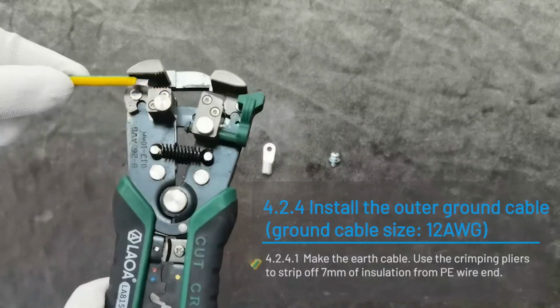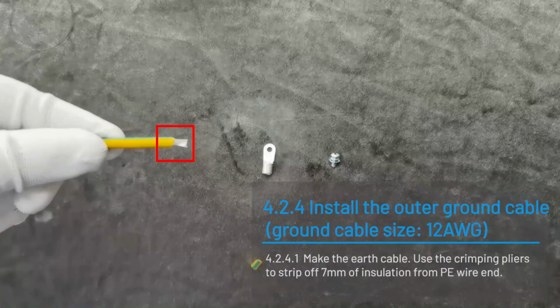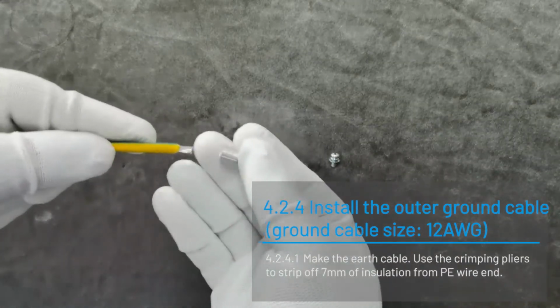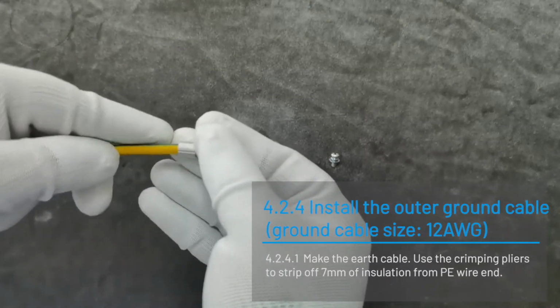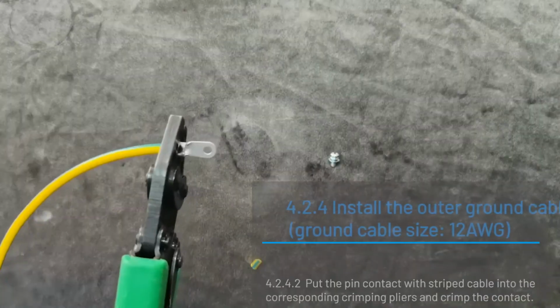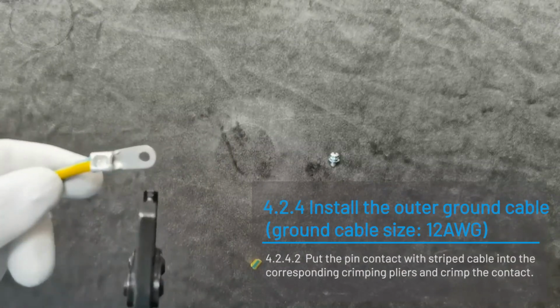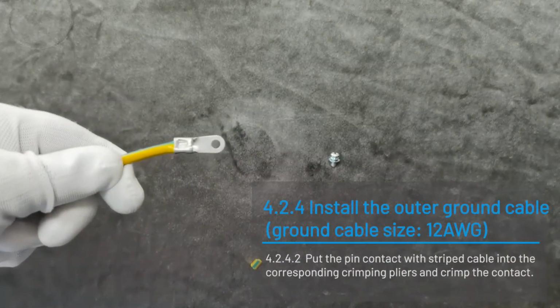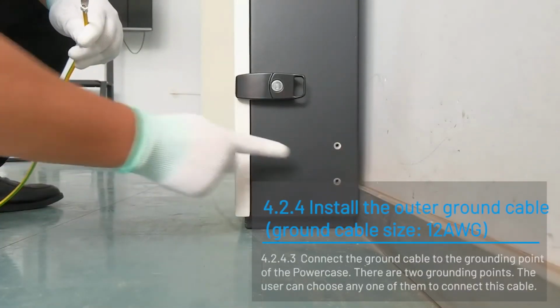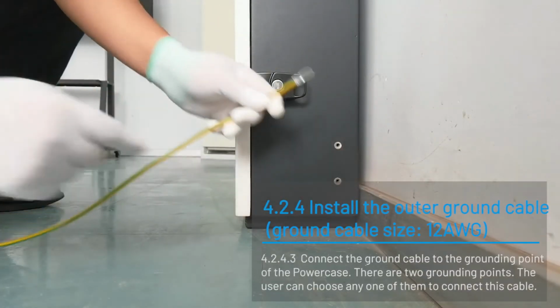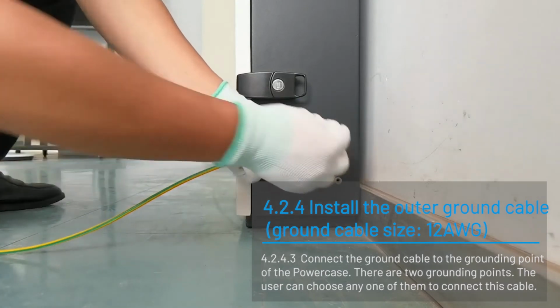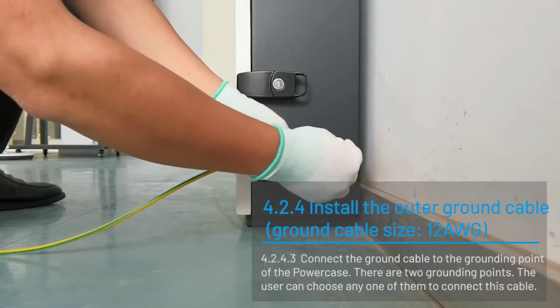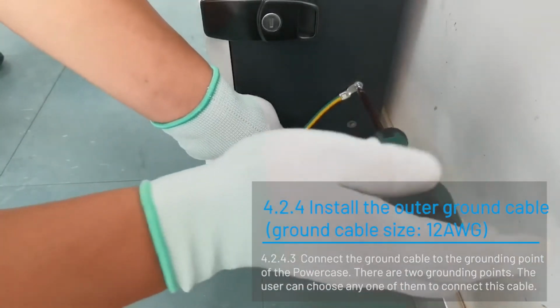Make the earth cable. Use the crimping pliers to strip off 7 mm of insulation from the PE wire end. Put the pin contact with the stripped cable into the corresponding crimping pliers and crimp the contact. Connect the ground cable to the grounding point of the power case. There are 2 grounding points. The user can choose any one of them to connect this cable.